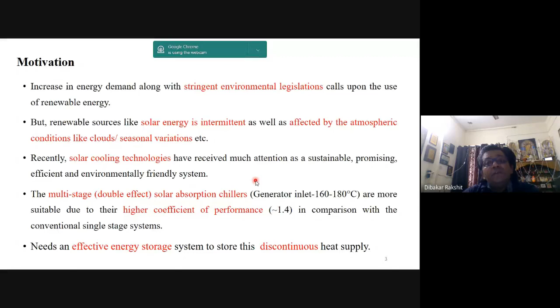Now the challenge is how to maintain this water temperature throughout, especially when coupled with solar cooling technology using absorption. This is where the requirement comes for thermal energy storage, or the thermal battery, which should be effective enough to hold heat for a long time. This allows a continuous, non-discontinuous supply of thermal energy to provide water at the required 160 to 180 degrees centigrade. This was the motivation for designing this thermal energy storage system or thermal battery.